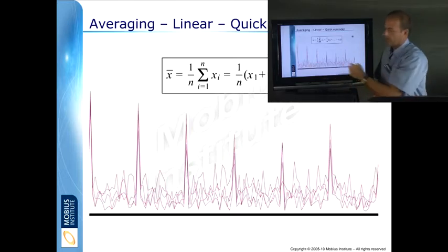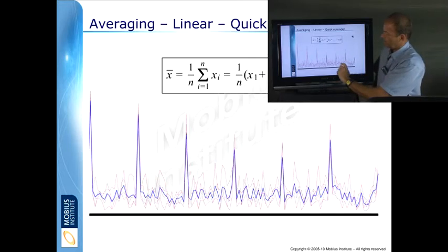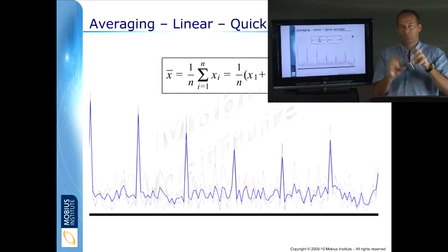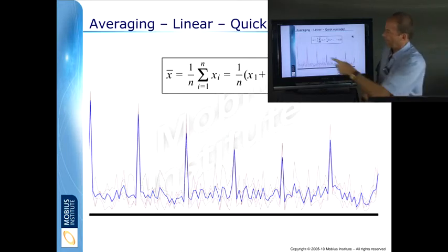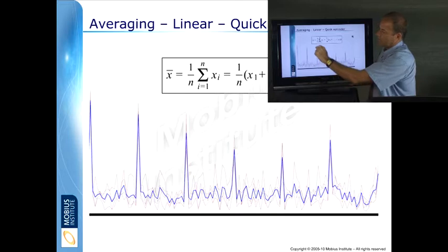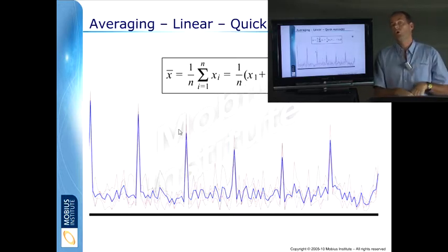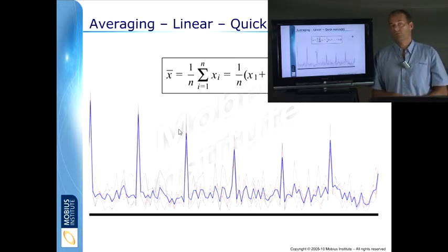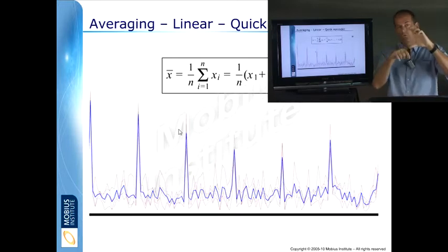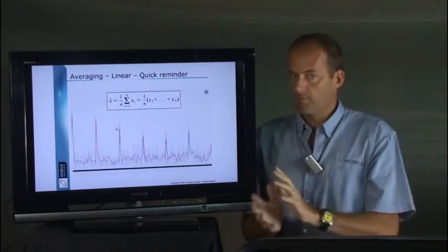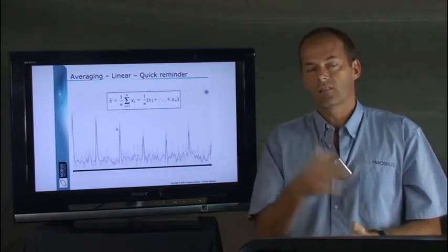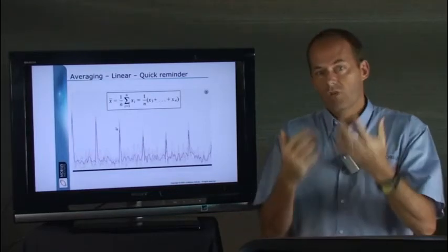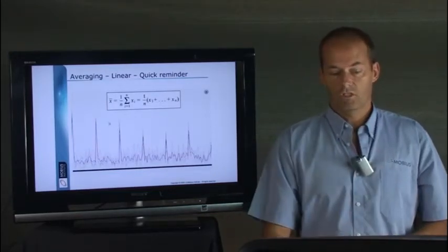Down here where we see a lot of variation, the average represents the average of the noise. But if you see a case where the average doesn't look like the same amplitude as the peaks, it means that there must have been more variation at those frequencies and you've just got something which is just an average of all that variation. Which may be okay for repeatability as long as you've got enough averages, but it doesn't really give you a representation of what the machine's doing.